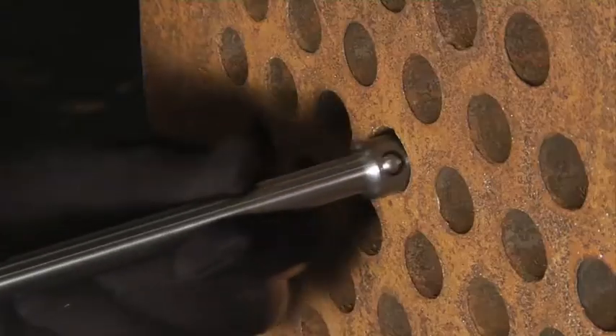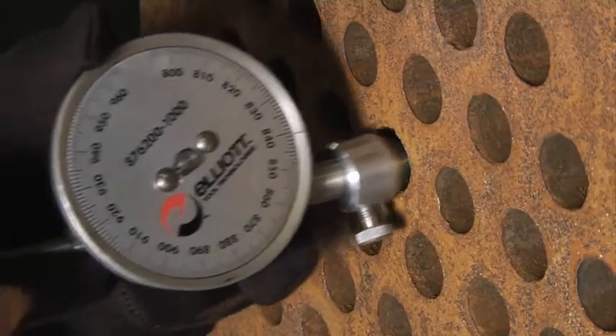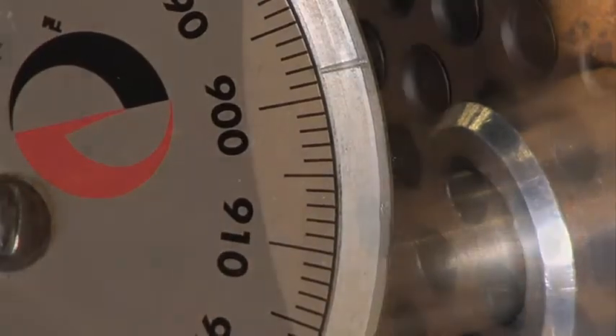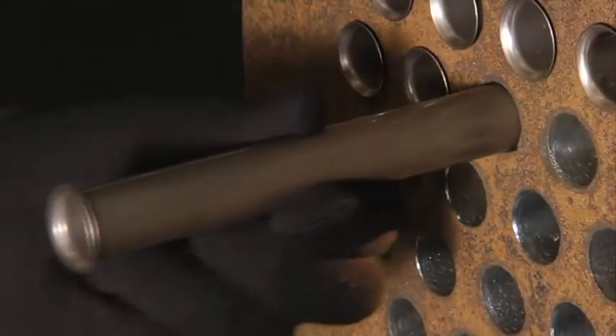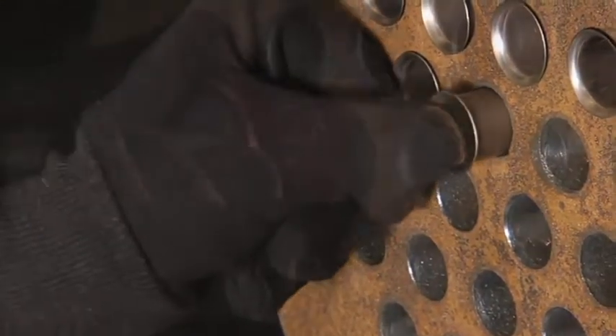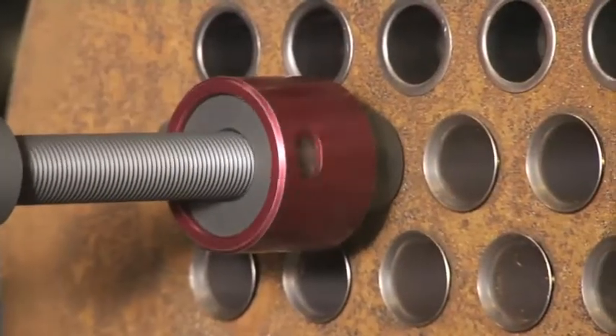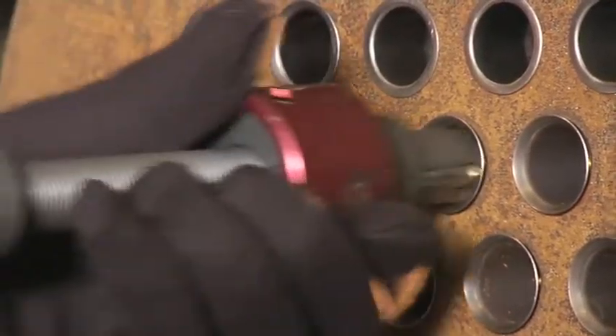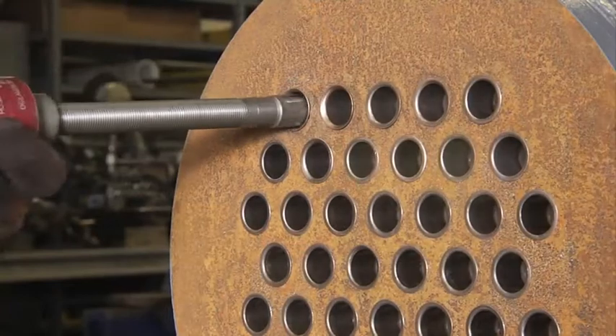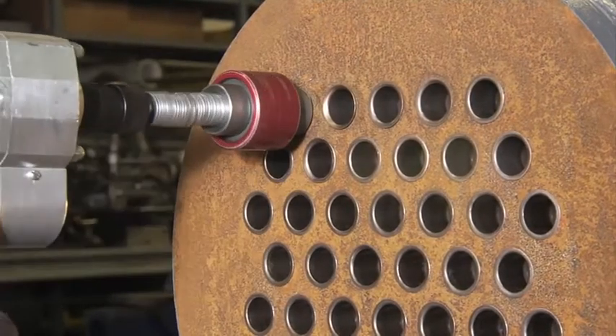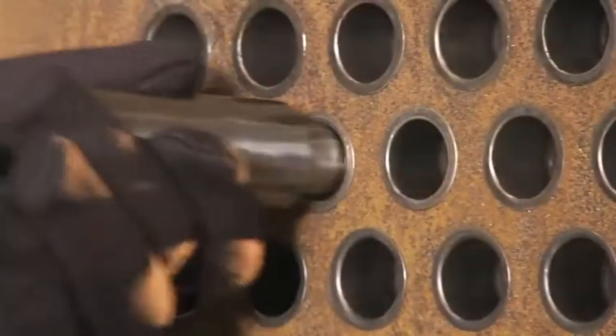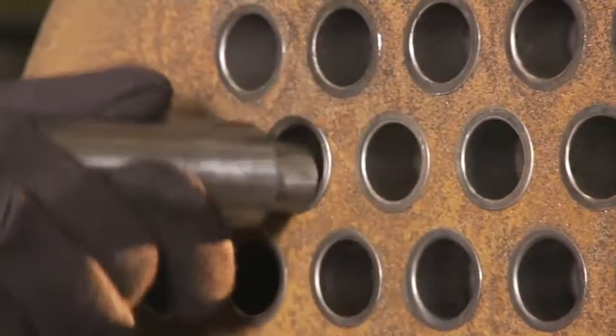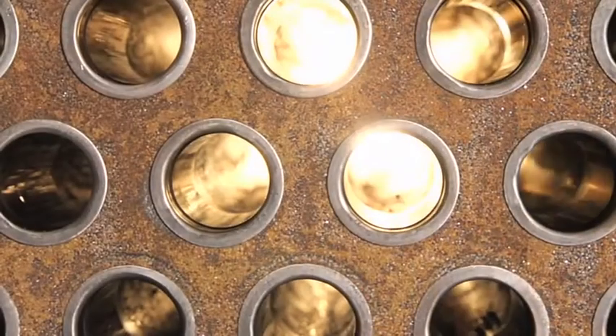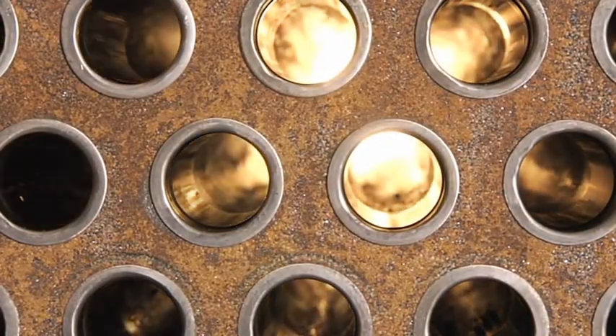Tube ID measurements are taken to determine expansion requirements, and the shields are inserted into each tube end. The flared end is expanded to a torque setting by use of a conventional tube expander. The downstream expansion is controlled with a mechanical stop. The last step is the final flare of the shields, so they conform to the tube-to-tube sheet profile.